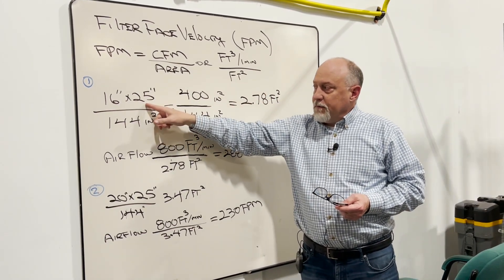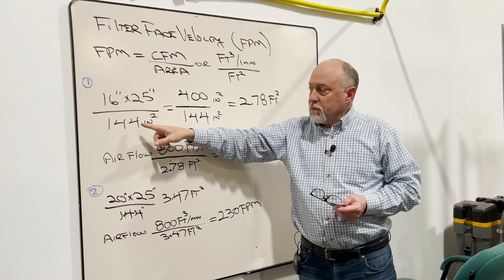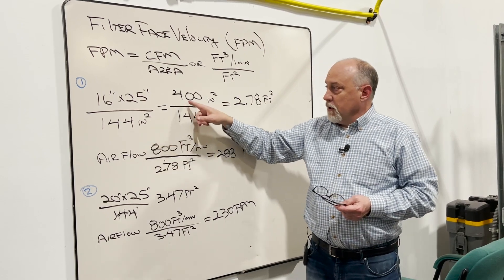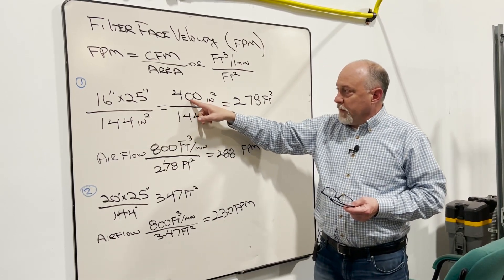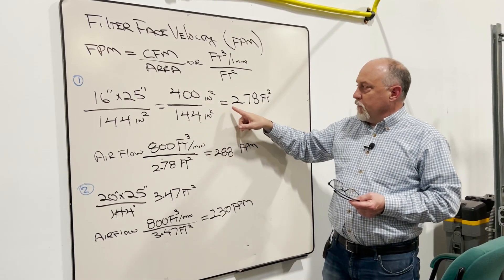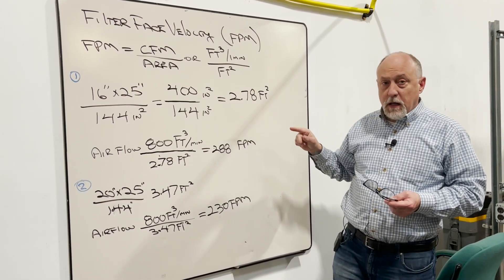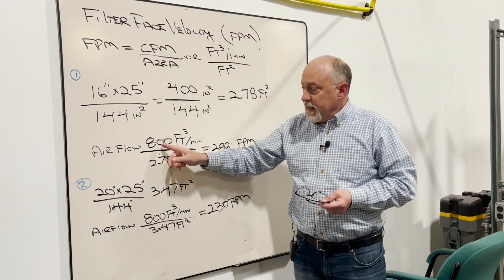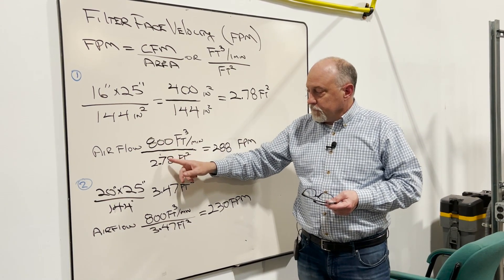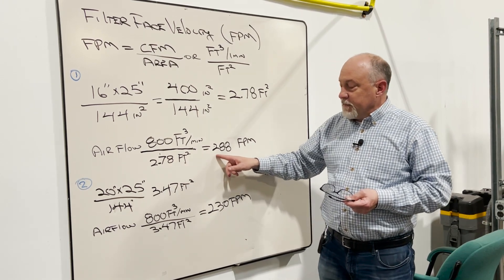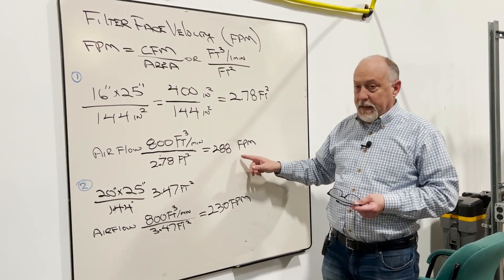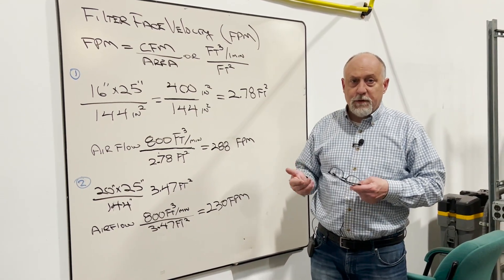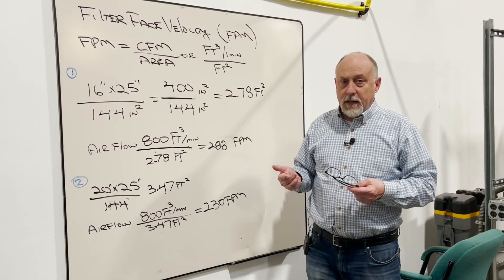So if we were to take a 16 by 25 filter, we have to first convert it to square feet by dividing by 144 inches squared. So 16 by 25 is 400, divided by 144 is 2.78 feet squared of filter media — that's all that is, it's just square feet of filter area. We take that 800 CFM divided by 2.78 feet, that gives us 288 feet per minute of velocity going across the filter. So that falls in that range of 250 to 500 — that ideal range is perfect.